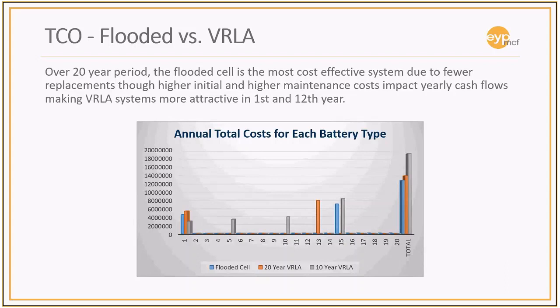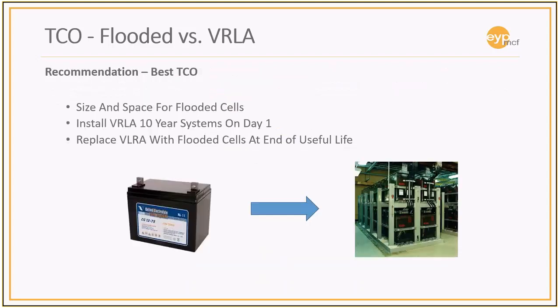But if you looked at the full 20 years, you could probably move together with a combination of these types of batteries. So the ultimate design recommendation was to put in a valve-regulated battery for day 1, but after the first replacement, switch to a flooded cell battery to get you to the full 20 years. So you're looking at one battery change-out in this particular TCO.